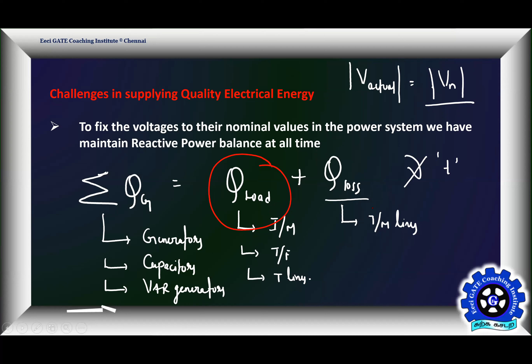then what happens? Then the actual voltage magnitudes will be equal to the nominal voltage magnitudes. For the same reason stated again, the load is not in our control. Load is not in our control. So we have to again catch up. We have to adjust our reactive power generation depending upon the load fluctuation, which is a challenge, which will lead to voltage fluctuation. So real power balance is responsible for frequency. Reactive power imbalance is responsible for voltage fluctuations in the power system network. Understand? So apart from these two challenges, what are the other challenges faced by electrical power system?